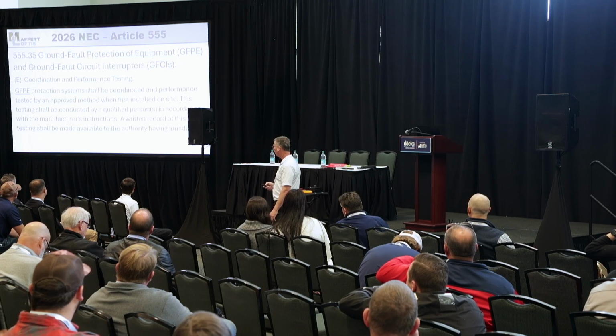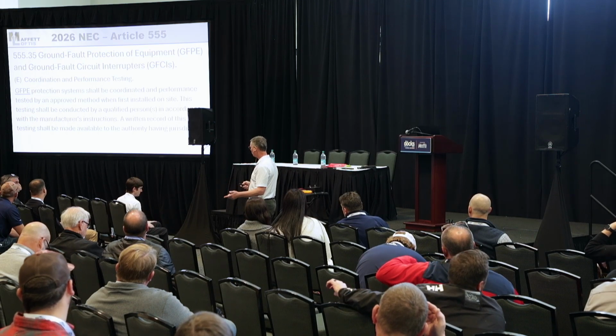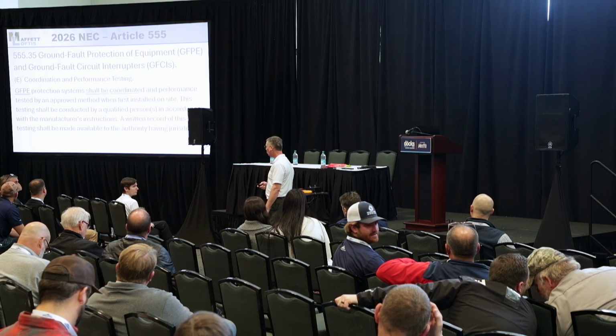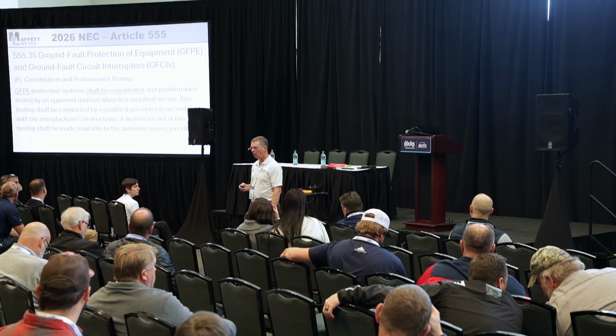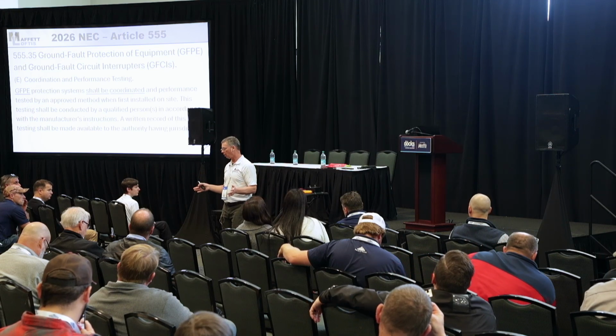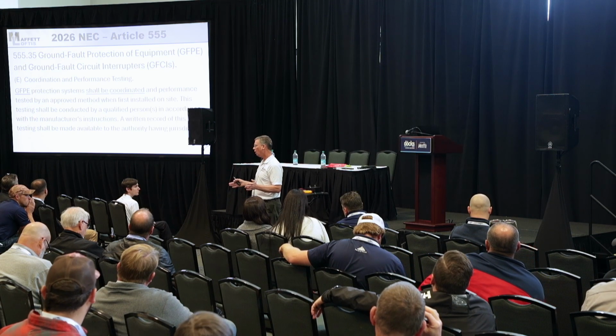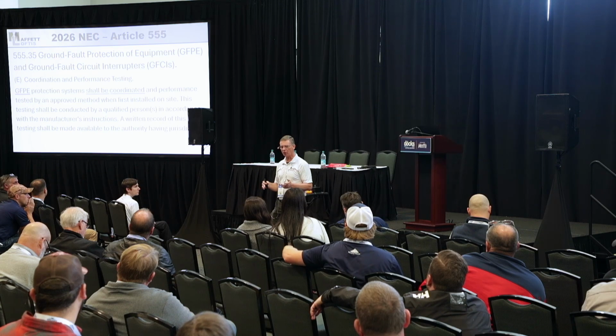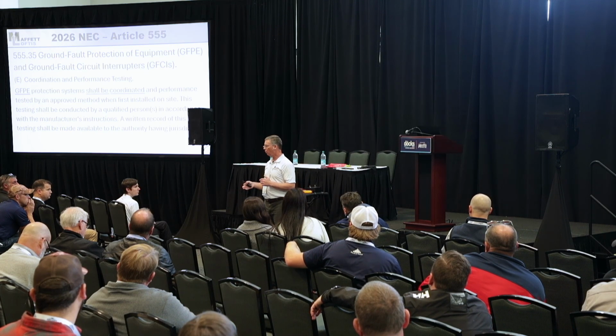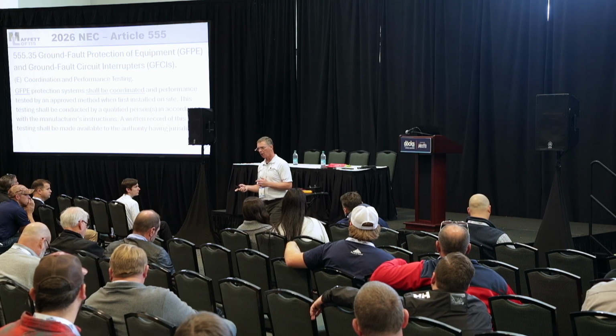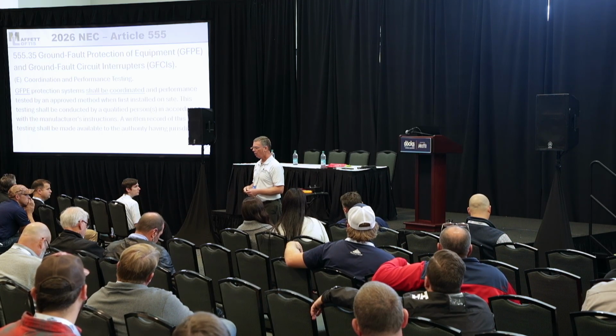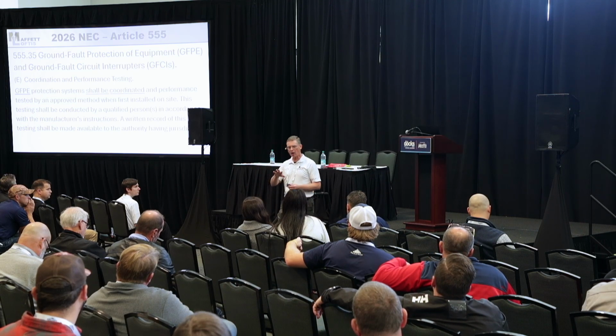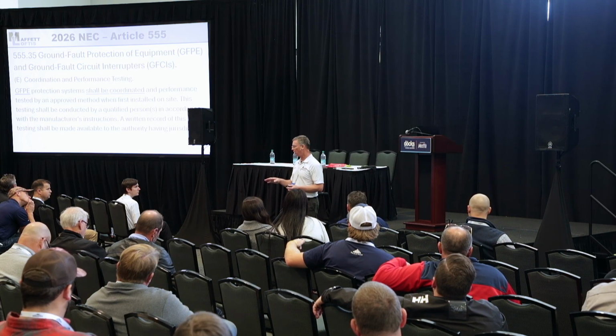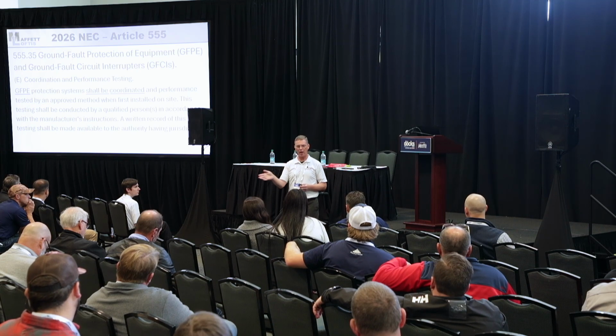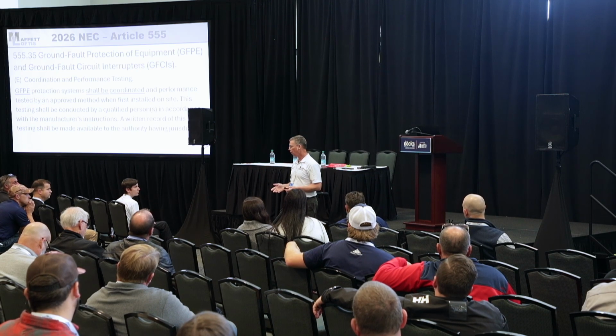Also, 555.35(E) says that you have to have GFPE protection, and it shall be coordinated. This is a big deal because GFPE has always been a headache, and I've taught a lot about ground fault protection. The 2023 says that the coordination would be permitted. In 2026, we're going to require it, because there have been a lot of problems with GFPE systems out there, and one bad boat tripping out the entire dock is not acceptable.